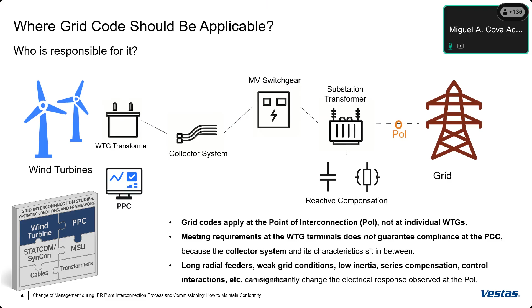This is something to keep in mind, especially during the sales part of a project, because if this is not crystal clear during the negotiation, we will face issues like long radial feeders, weak grid connections, low inertia, series compensation, and control interactions with nearby plants that weren't considered when the proposal was submitted to a specific customer, deviating from the scope of the project. If that's not clear when the project changes hands, expectations will be very different.